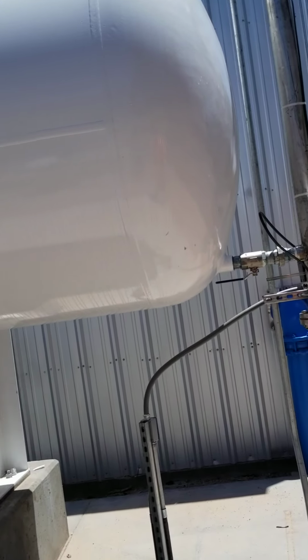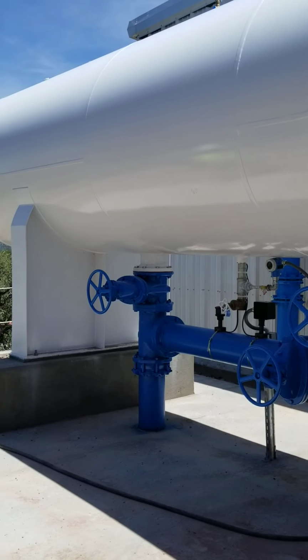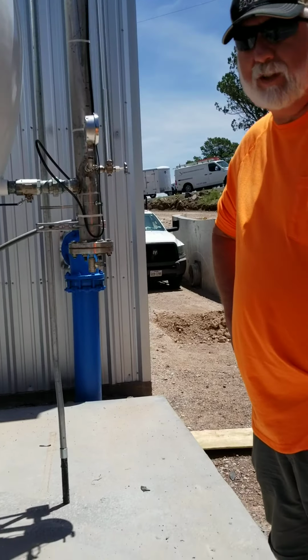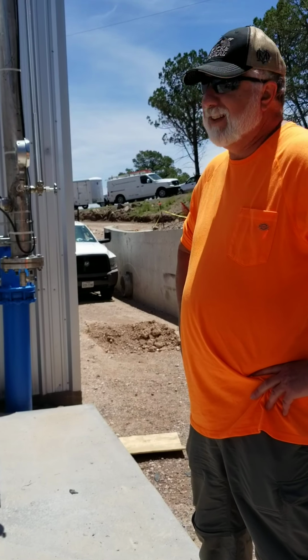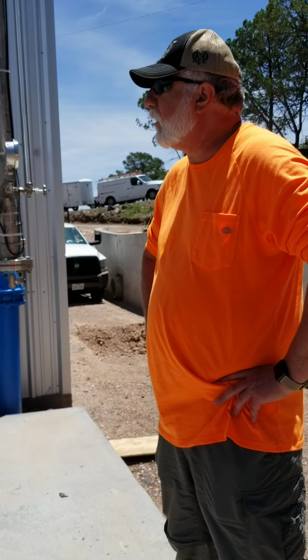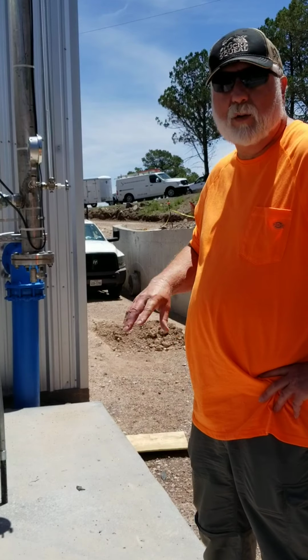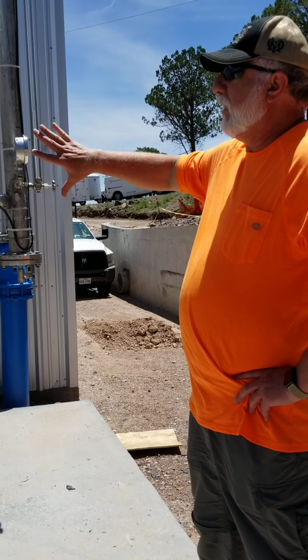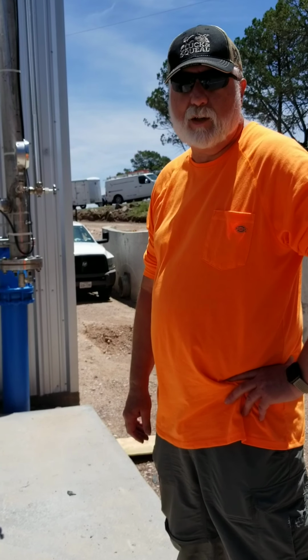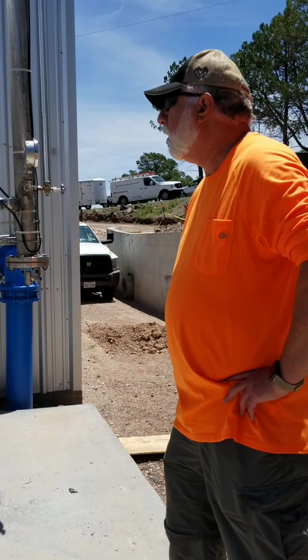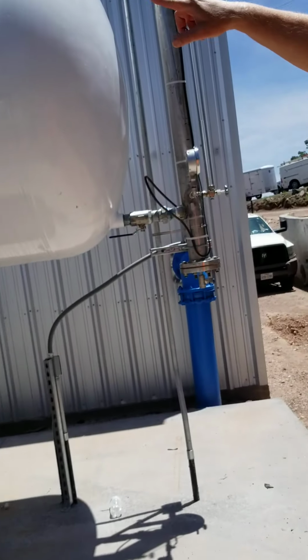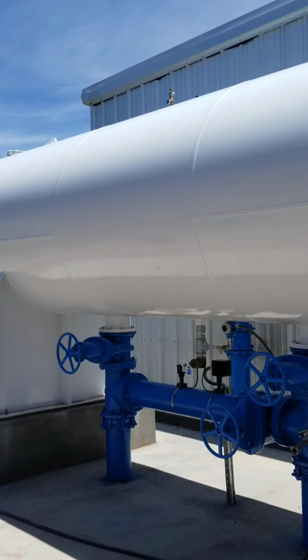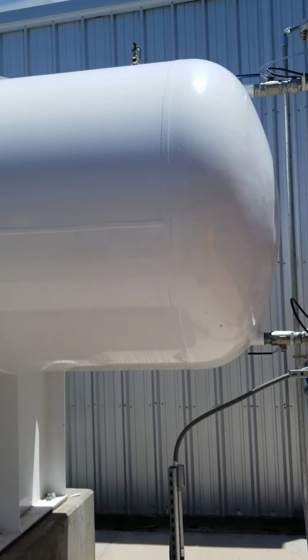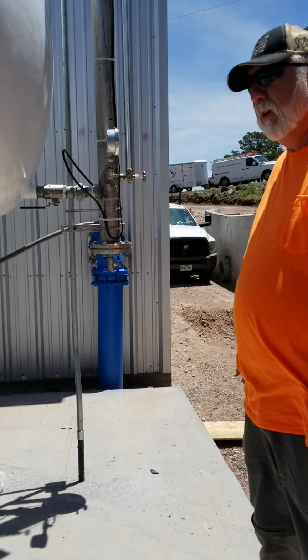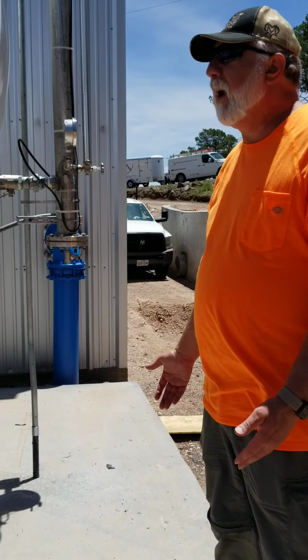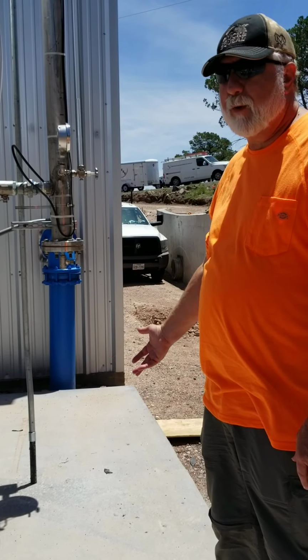It is designed and rated for 250 psi working pressure. Per ASME code, which these tanks are all built to, the tank is designed and tested at 1.3 times that, so there's a safety factor built into the fabrication, the thickness of the steel, and the testing of the tank to ensure that it will work at 250 psi and still have that safety factor. On the top of the tank, there are two safety relief valves, one on this end and one towards the other end. Those are set at 250 psi, so those are additional safeties: if a pump turned on and never turned off, and the pressure got up high enough, they would open up and relieve pressure off the tank to keep it from overpressurizing.